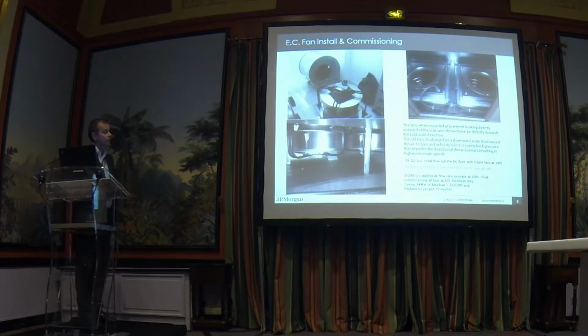So the savings, we've increased the data center flow rate by 21,000 litres a second of air. So commissioning the fans at 65% at the end of it. So we were running almost half. So the savings of 140 kilowatts, moving the same amount of air in the data center. And that's a base load. So when you're computing that out at about 12 pence per kilowatt hour, it's £147,000 a year.